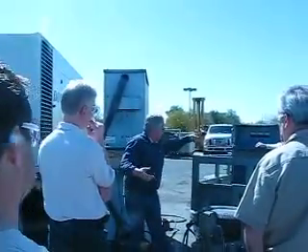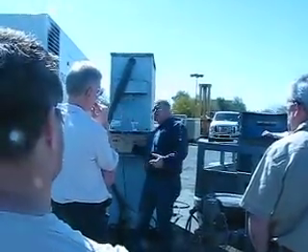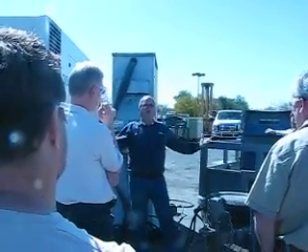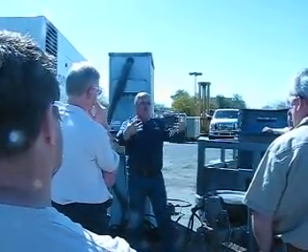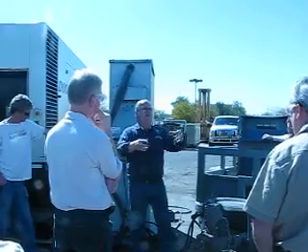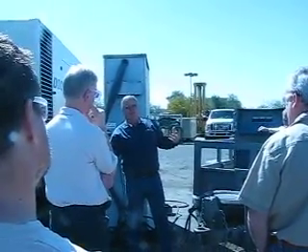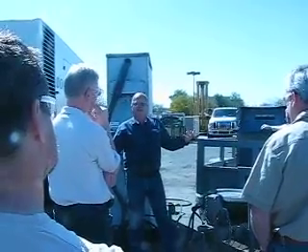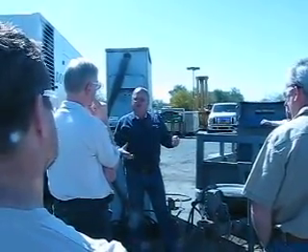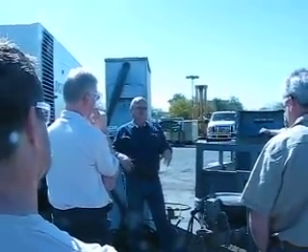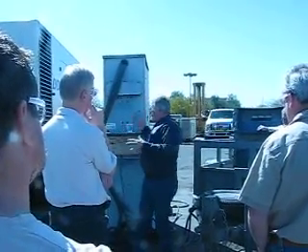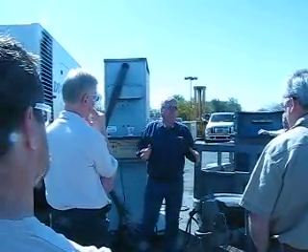So between the resistive and the reactive, now you can create an actual full load test on the prime mover and the alternator with the amps at the same time. Bringing it all together. So that's why there's reactive load banks.